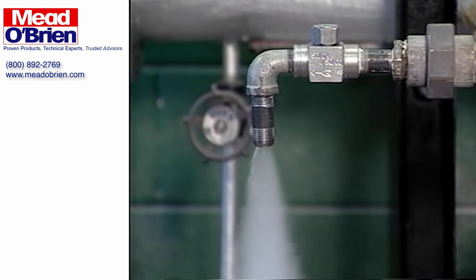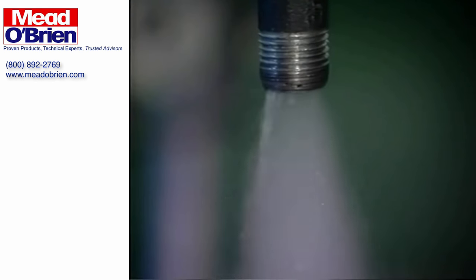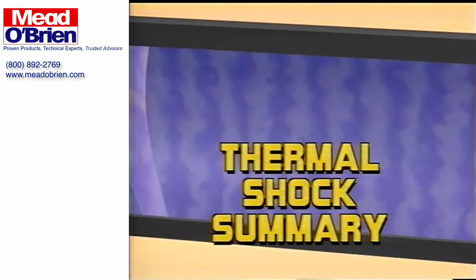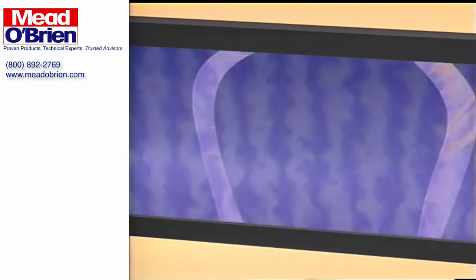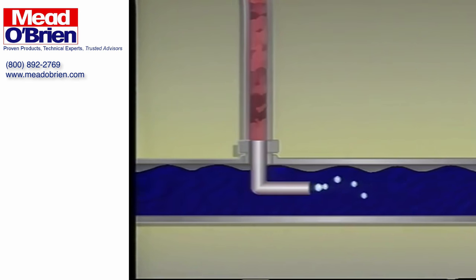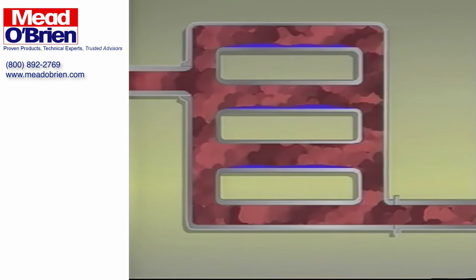Malfunctioning steam traps may also contribute to thermal shock followed by water hammer. A steam trap that has failed open injects live steam directly into the condensate return line. If this steam is mixed with return line condensate of sufficiently low temperature, it will immediately collapse and thermal shock will follow. To prevent water hammer due to thermal shock, you must reduce the concentration of collapsing steam bubbles in the condensate. If flashing condensate must be discharged into a cool condensate line, it should be discharged in the direction of condensate flow and away from the pipe wall. Heat exchanger tubes must always be filled from the supply end only.